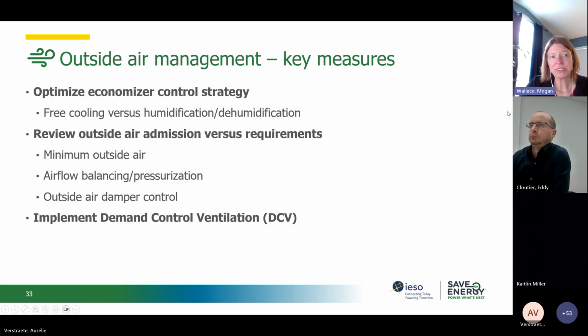To review the key measures for outdoor air management, you want to look at optimizing the economizer control strategy. Review the outside air admission versus the requirements, so the minimum outside air requirements, the airflow balancing and pressurization, and the outside air damper control. And also look at implementing a demand control ventilation system.